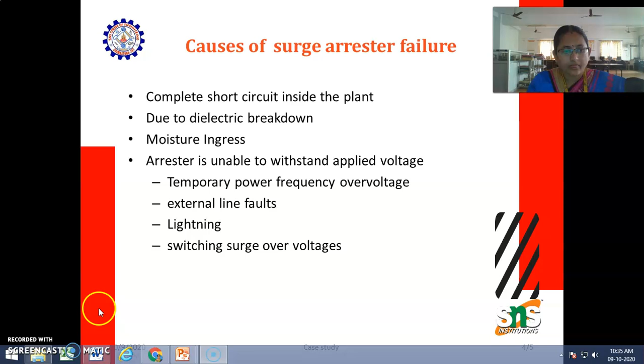Surge arrestor failure also occurs due to exceeding the upper limit voltage. It is not possible to estimate the lightning current and voltage, although it is possible to take some precautions with the surge arrestor placed at a certain distance. It is always possible that the upper limit is exceeded. Even if the selection of the surge arrestor is made according to the requirements of installation, it is not possible to get rid of this risk literally. Therefore, it is necessary to use a surge arrestor stabilizing device to prevent lightning strokes and static electricity induced voltages and currents from damaging the surge arrestor.